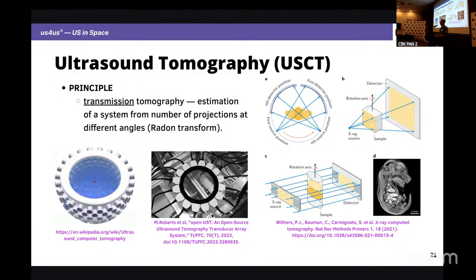Yes, it is a classical method for 3D scanning of a patient using X-ray. The concept in ultrasound is almost exactly the same. As you can see, there are different geometrical architectures for this, but one of these is also a ring, just like in standard computer tomography. You have this ring, this pipe that you put the patient in, and the wave goes all around you. Yes, the source of X-ray goes all around you and is detected at the opposite side. So this is a transmission mode. In normal ultrasound, you have backscatter mode, when you transmit ultrasound and get the backscattered signal, in a reflection mode. In this mode, we are going through the object, casting the rays through it and receiving them at the opposite side.